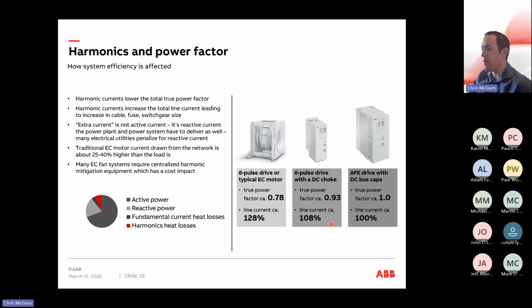Now, our standard 6-pulse ABB drives do have somewhat of a harmonic prevention through the use of a DC choke, which helps the power factor by bringing it up to 0.93. But this still has your line current at 108%. It's still not perfect. You're still drawing more power than you need to.